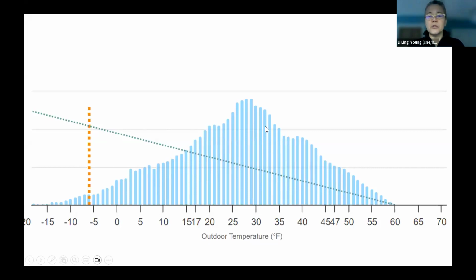Looking at the distribution of where the blue bars are, you can really see why it's important to understand what the heating system, or in this case heat pumps, are doing in these part load conditions, because look how much energy is consumed in these part load conditions. 20% of all the energy we use to heat our buildings is consumed at 40 degrees and warmer. 40 degrees, we hardly even think of that as being the heating season, and yet we spend so much time at 40 degrees and warmer over the course of a winter that it accounts for 1/5 of all the heating energy we use in a heating season.